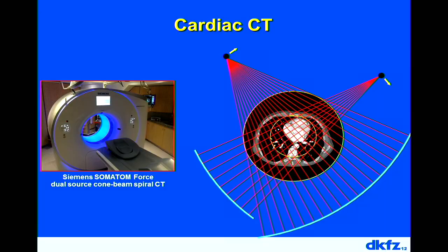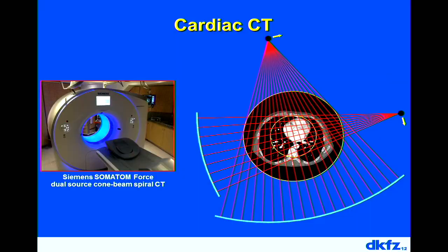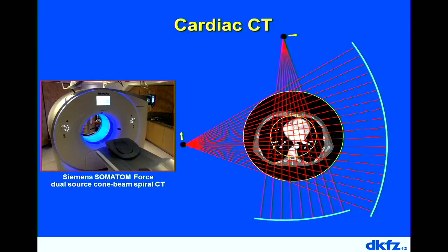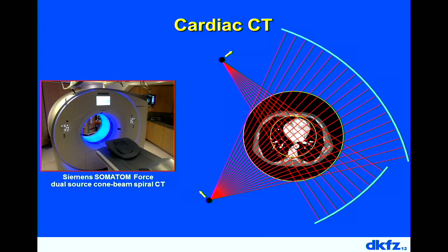In cardiac CT, one vendor has a special system with two X-ray sources and two detectors. To acquire data for a CT image, 180 degrees of rotation is needed. For a single X-ray tube system, the scanner rotates 180 degrees; for a dual-source system, it only needs 90 degrees. So the temporal resolution achievable with a dual-source system is twice as high as with a single-source system — this is a dedicated cardiac CT system.